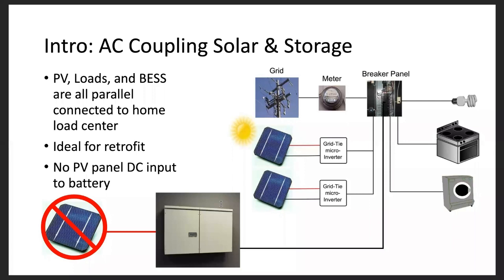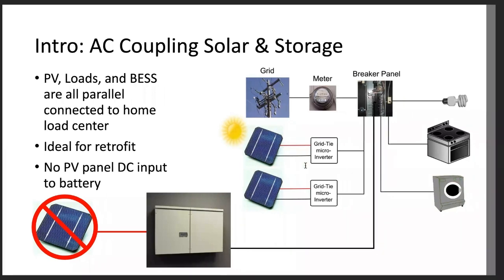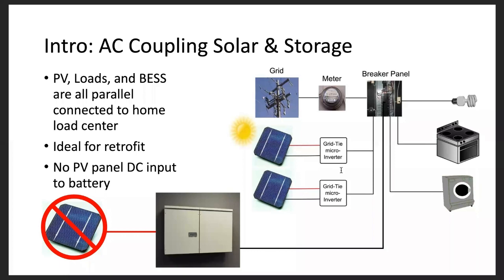And a pretty critical point to make here is that because it is AC coupled, there is no PV module DC input to the battery. All of your PV must have its own dedicated either microinverter or string inverter. The PV inverter must be supplied.